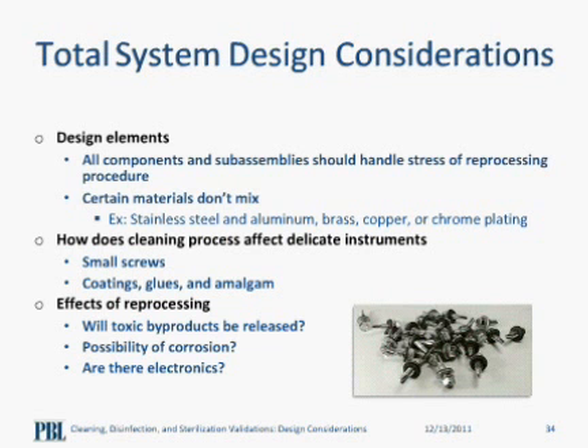What are the effects of the selected cleaning process on delicate instruments? Choosing the appropriate method in the processing depends on how it affects the device. For example, the use of ultrasonic washers. This method of cleaning is popular because of its efficacy in removing debris from hard-to-reach areas. It may be perfect for this purpose, but consider the fact that ultrasonic energy can also loosen tiny screws of delicate instruments and might destroy coatings, glues, and amalgam in the devices. We have to bear in mind that adequate reprocessing of reusable devices is vital to protecting patient safety.